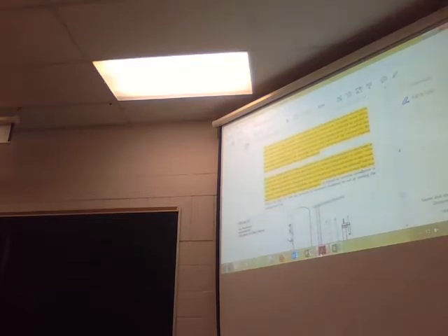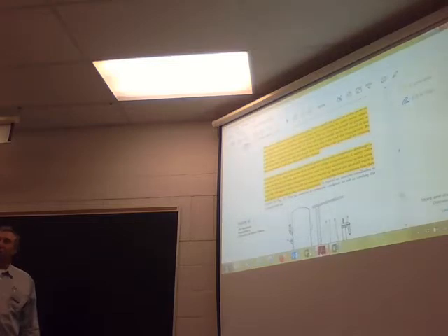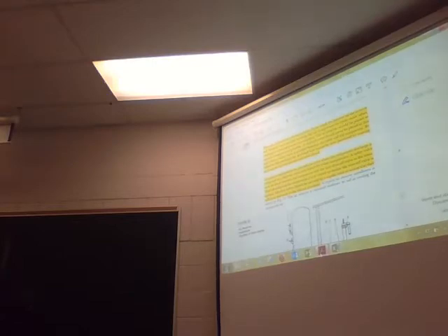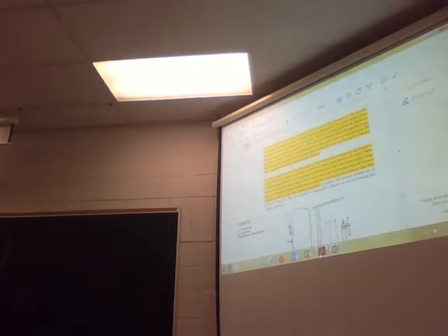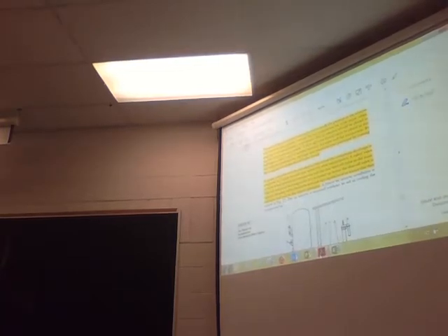Size of receiver is imperative, right? Because what did we talk about earlier? We had too small of a receiver, the compressor was going to come on and off more. So the size of the receiver merits attention. If too small, the pressure in the receiver will fluctuate more rapidly, causing the air compressor to cycle more often, resulting in increased power consumption. You want to keep a job being valuable to your employer.